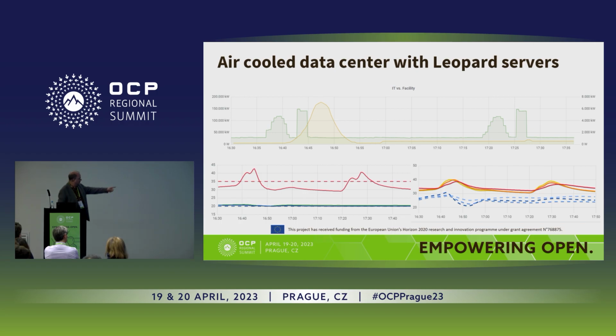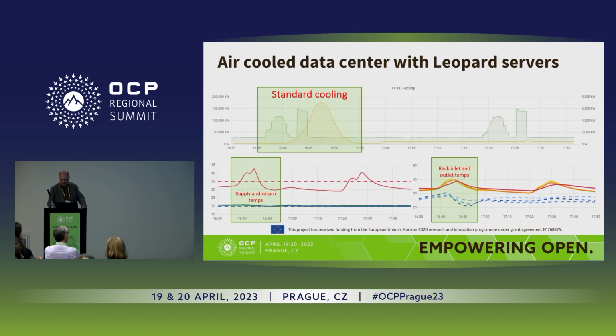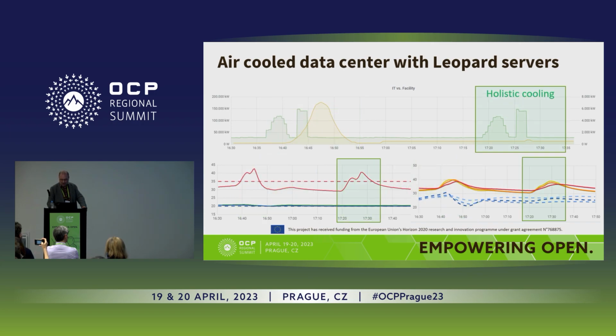You can see what happens to the supply and return. The supply temperature is the blue line there. The supply temperature to the front of the servers is still the same. No problem. But that's one of the issues. So that's standard cooling, and that's holistic cooling control. So that was one experiment that we managed to do.